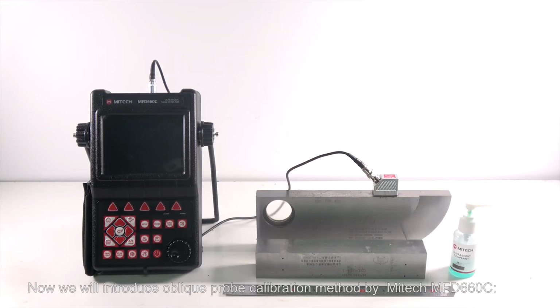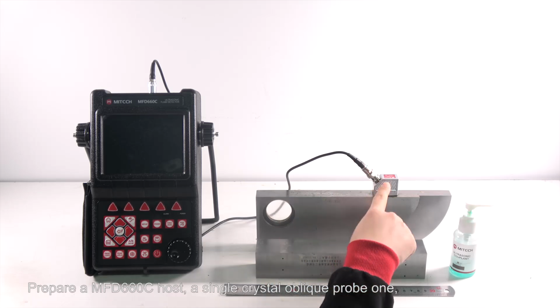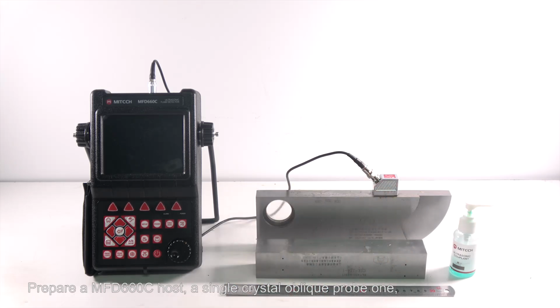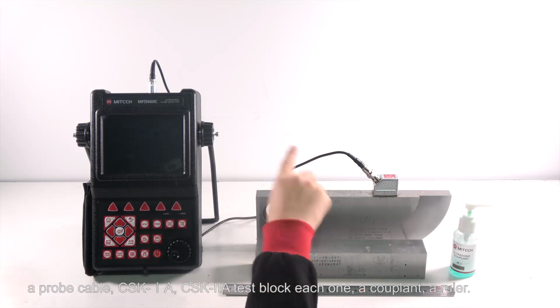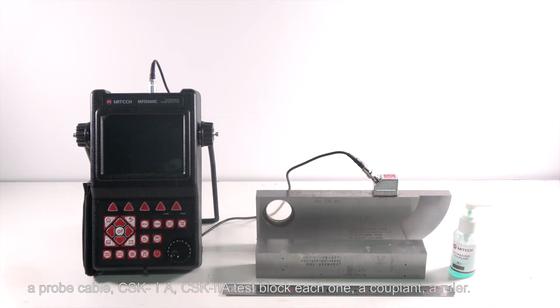Now we will introduce the oblique probe calibration method for the Mitech MFD660C. Prepare an MFD660C host, a single crystal oblique probe, a probe cable, a CSK1A and a CSK2A test block, each one.